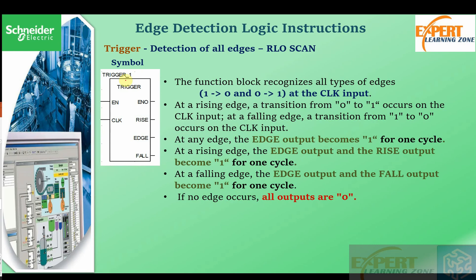Next we look at the trigger function, which is detection of all edges. The trigger function detects all edges — it is a combination of both the falling edge trigger and rising edge trigger. The function block recognizes all types of edges from one to zero and zero to one at the clock input. At the rising edge, the edge output and the rise output become one for one clock cycle. At the falling edge, the edge output and the fall output become one for one clock cycle.